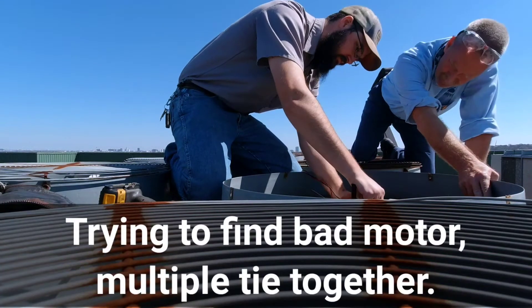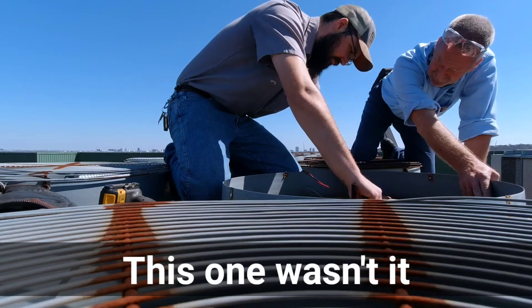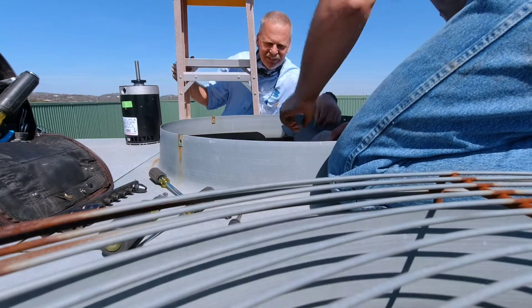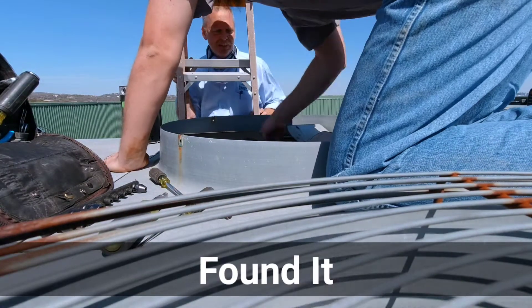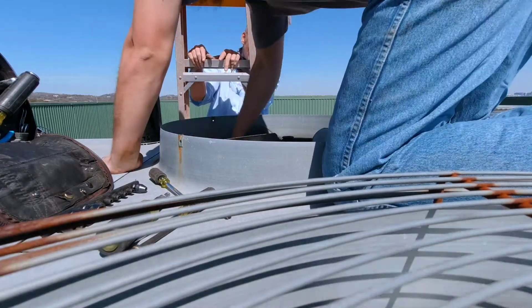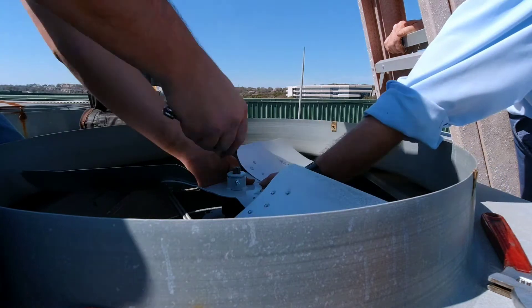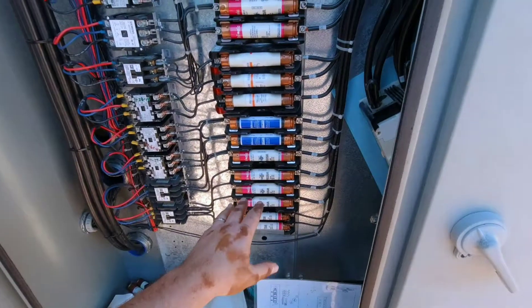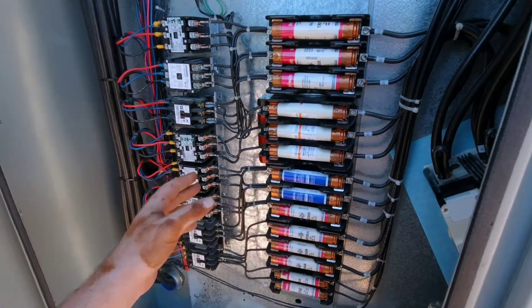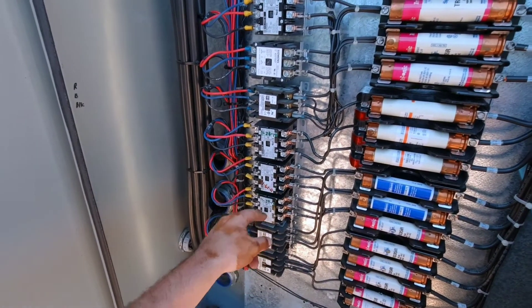Let's get started. So just real quick — they had a downed condenser fan motor. These two fuses blew, shorted to ground. This fuse block runs these three contacts.